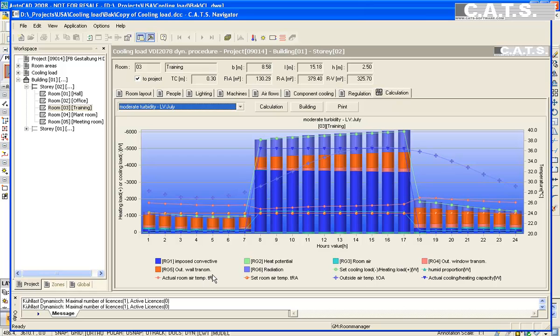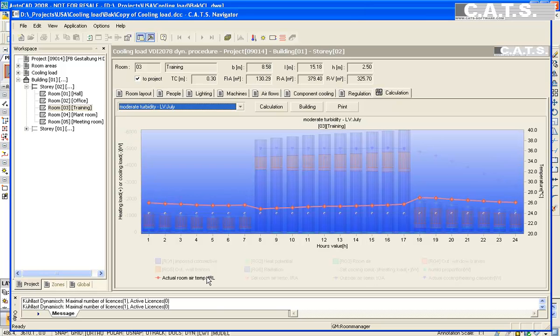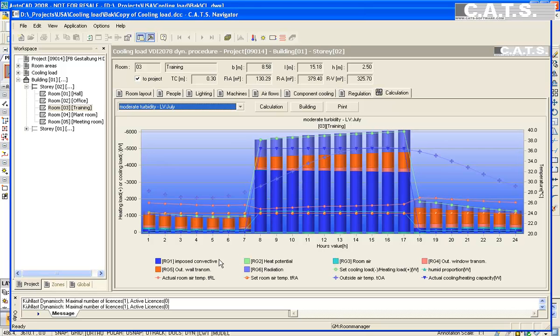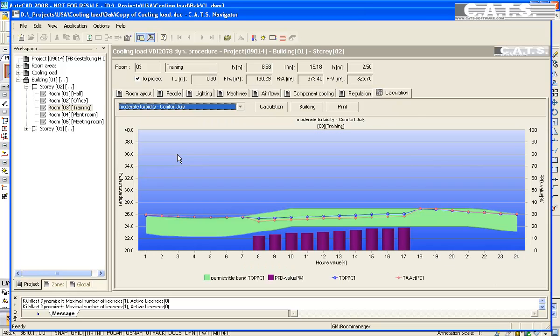The room air temperature increases over a setpoint to 26 degrees Celsius during the occupied period. The comfort zone indicates that we are in the allowable limits of the comfort zone at 16% less capacity. The percentage of dissatisfied people rises only slightly.